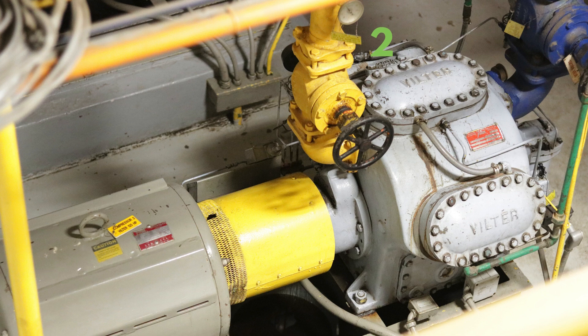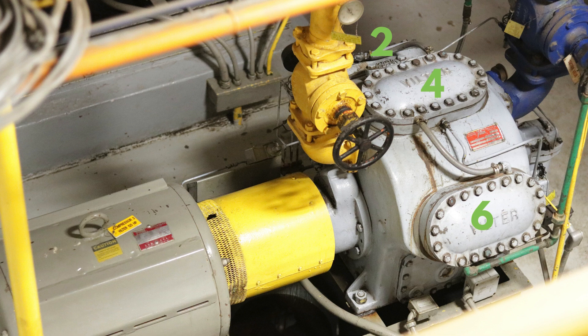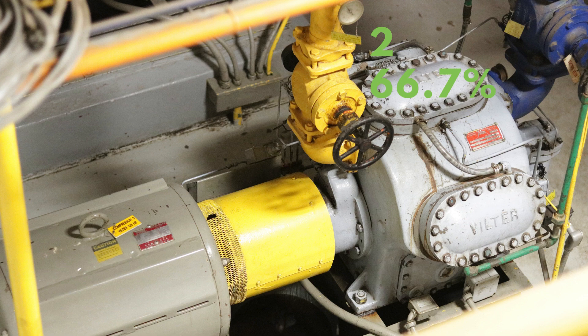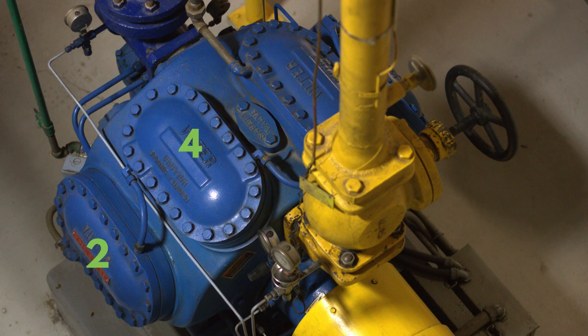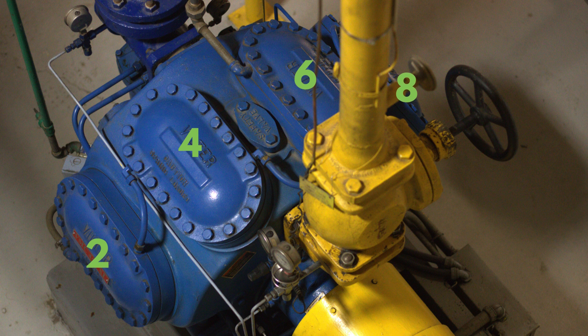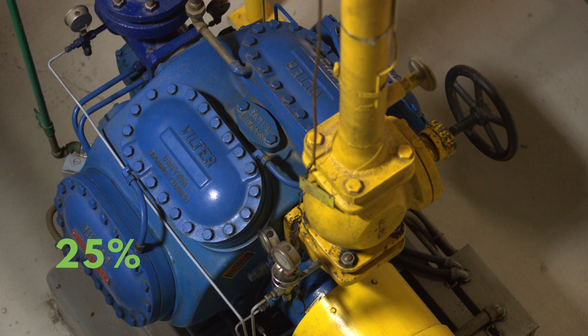Unloading in reciprocating compressors typically occurs in two-cylinder increments. For example, a six-cylinder compressor could unload down to four or two cylinders corresponding to 66.7% or 33.3% capacity. An eight-cylinder compressor could unload down to six, four, or two cylinders or 75%, 50%, or 25% capacity.